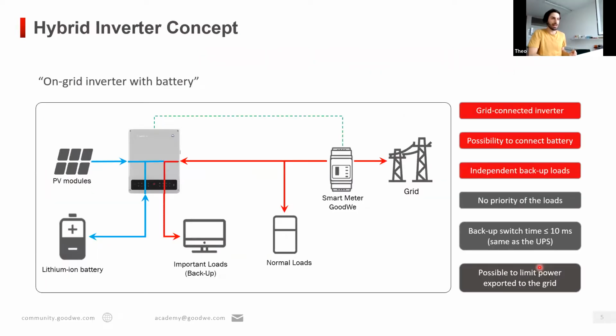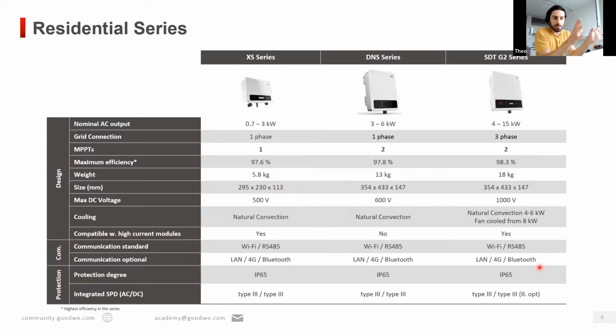Apart from the very good efficiency that these inverters offer, they also come with several different communication standards. We offer Wi-Fi communication, communication with straight wires, so LAN or RS485. If you live in a remote area, we also offer 4G connection. So directly with a SIM card, you can connect to the internet and still monitor your plant through that. So these are the PV inverters we have. These are pure PV inverters, and they work very well.